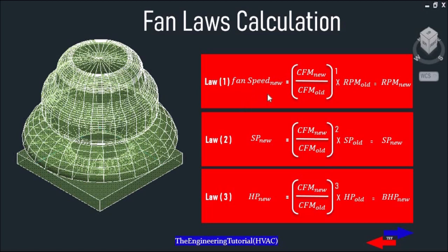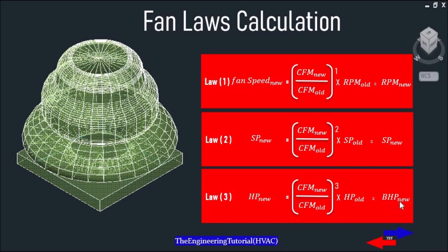We'll use the same formulas as before: Fan Speed New = (CFM New ÷ CFM Old) × RPM Old. Static Pressure New = (CFM New ÷ CFM Old)² × Static Pressure Old. And Brake Horsepower New = (CFM New ÷ CFM Old)³ × Horsepower Old.